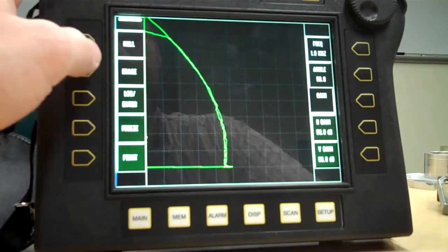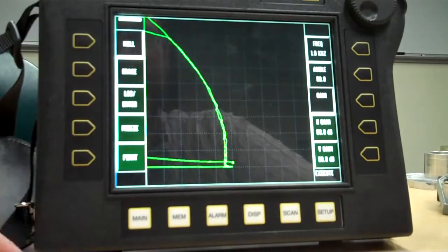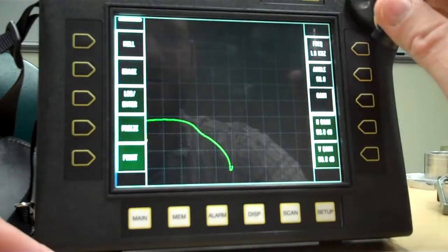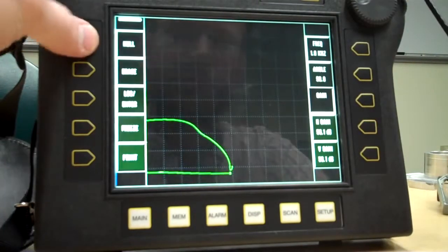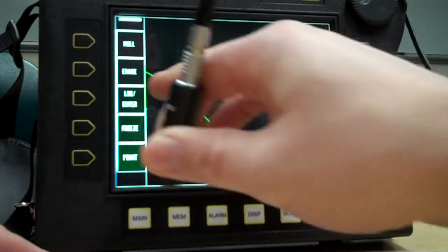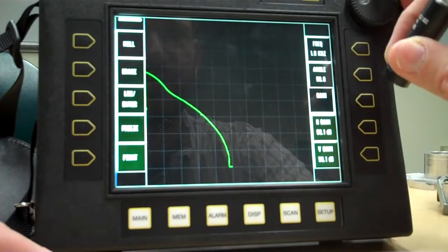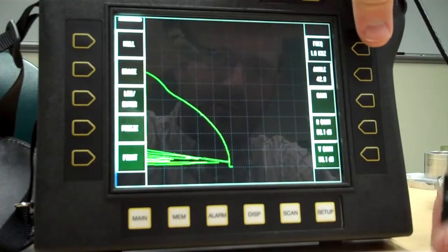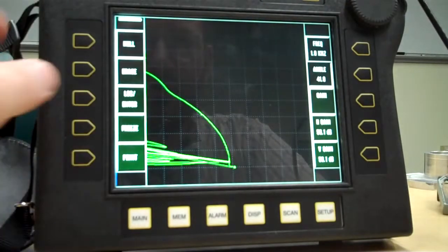And what I did was lower the frequency, so I increased the standard depth of penetration. There's my little hook thing at the end. There we go. So 50 dB is too low. Let's go about 56 and null. There's the start of my edge effect. So I'm going to take my angle just for fun, rotate it around a little bit.